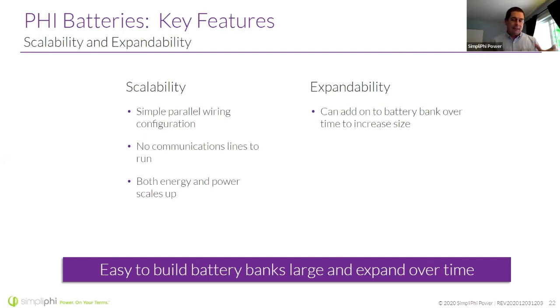So when we talk about that C/2 rate, we have a 3.8 kilowatt hour battery that can be discharged at a C/2 rate. That 3.8 divided by 2 means you get 1.9 kilowatts of power out of that battery. So I'm not only building up in 3.8 kilowatt hour chunks, I'm also adding 1.9 kilowatts of power with each additional battery. So you're scalable on both the energy and power side.